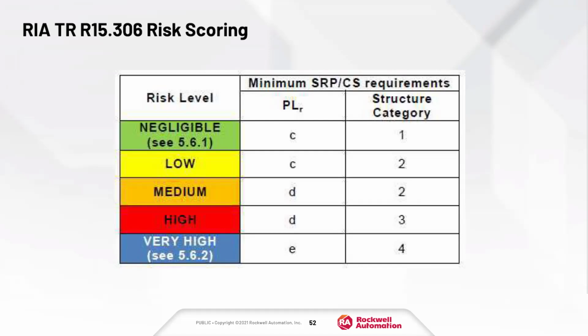So we're not worried about something failing in a way that shuts the machine down. We're worried about something failing and the machine still runs and you don't know it failed. So that's where adding that redundancy and that checking and all the other things we do takes it from one incident taking it out to now you have to have two distinct incidents take it out. And the likelihood of that happening with good quality equipment to both at the same time, and you don't know one of them failed, is very low. So again, that's where one plus one equals a million or more. So when we have these structures, category two, category three, category four, that's what they're talking about. It's the physical design of the circuit.